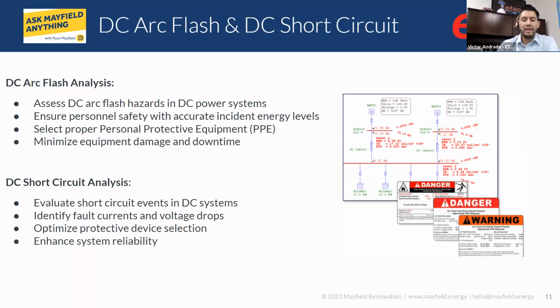This is a real danger, right? This explosion can cause severe burns, sometimes blowing the person many feet away from the equipment, bone fractures, loss of hearing because it releases a lot of noise, and loss of sight because sometimes it's so bright and there's shrapnel that gets released during the explosion. A lot of people go blind, so we want to make sure that everyone is protected, and that's what the arc flash study accomplishes. Safety, right? Human safety.